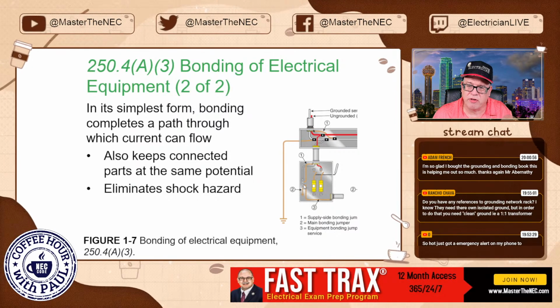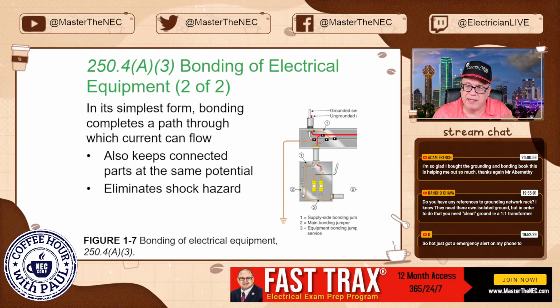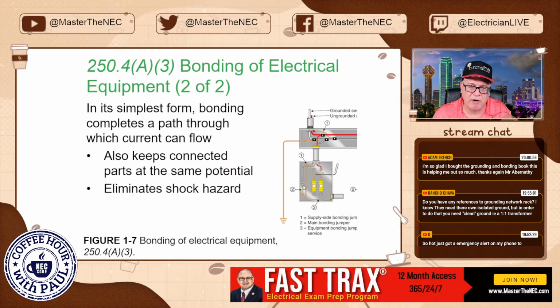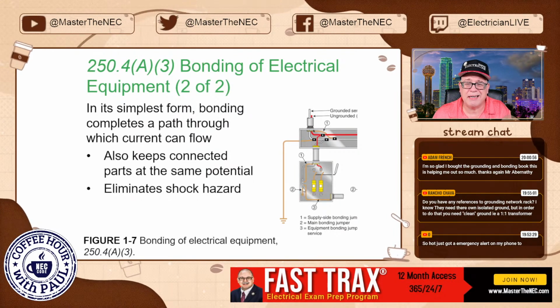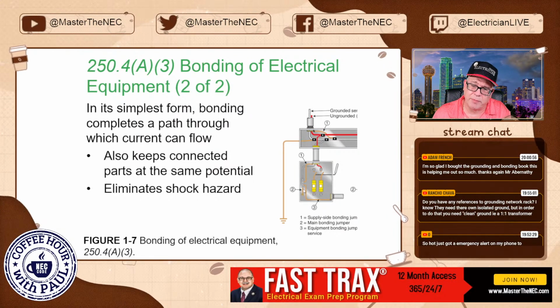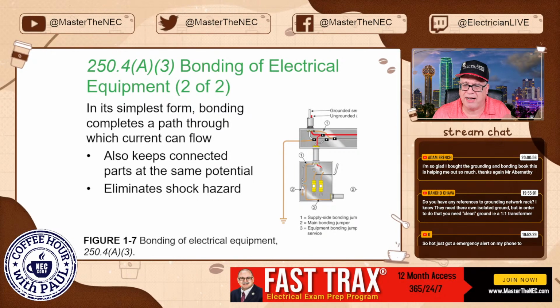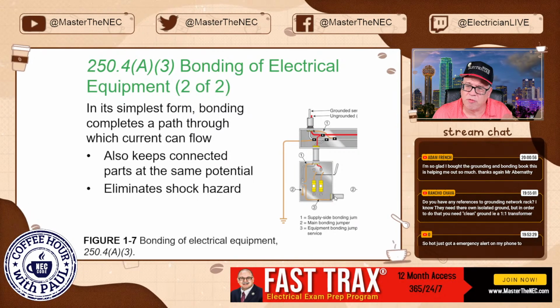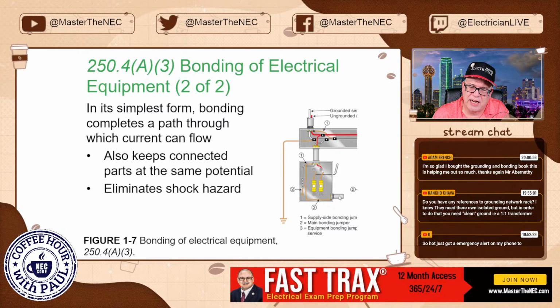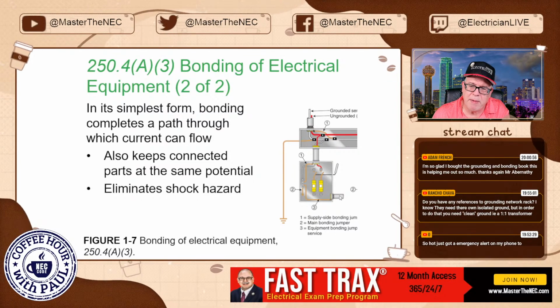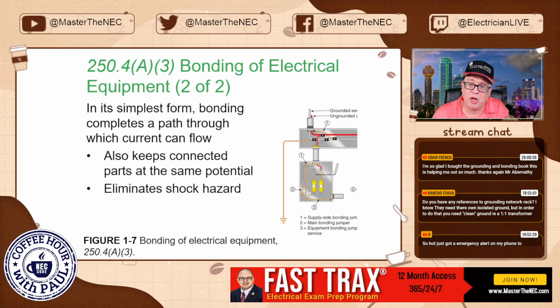This is the main bonding jumper connecting what? The enclosure to the actual grounded conductor. Also connecting any, in this case, it shows like a jumper, but could have been a green screw in there. Could have been fine, right? And then this one right here, this is obviously on the load side. So that is called an equipment bonding jumper because it's on the load side of the service.